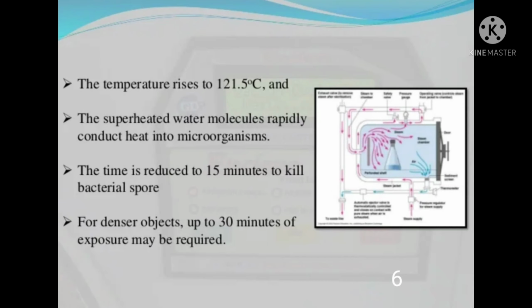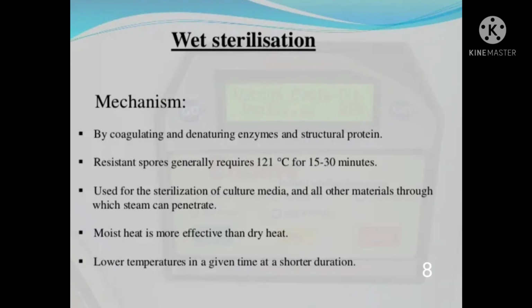The temperature rises up to 121.5 degrees centigrade and the superheated water molecules rapidly conduct heat into the microorganisms. This time is reduced to 15 minutes to kill the bacterial spores. For denser objects like our linen and dressing material, up to 30 minutes of exposure may be required. Autoclaving is basically wet sterilization or moist heat sterilization. The mechanism of autoclaving is by coagulating and denaturing enzymes and structural proteins of microbes and microbial spores. The resistant spore generally requires 121 degrees centigrade for 15 to 30 minutes. It is used for sterilization of culture media and all other materials through which steam can penetrate. Moist heat is more effective than dry heat.